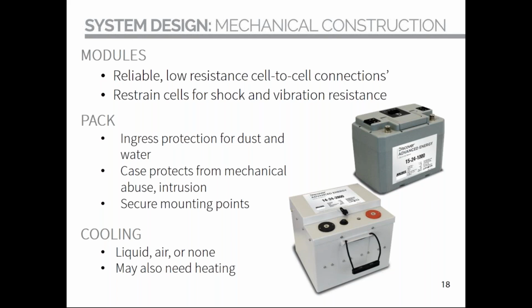Cell terminals have to be connected electrically in a way that's reliable, repeatable, and low resistance. On smaller cells this is generally done by welding, laser or ultrasonic. On larger cells, they're more likely to have threaded screw connections whose torque must be carefully controlled. As Brendon highlighted, they've selected cells which have screw connections.